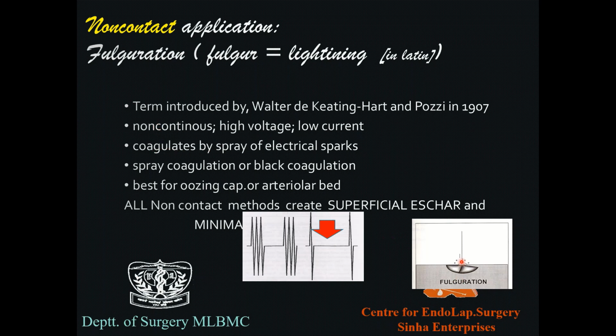See, it is spraying. The spray coagulation or black coagulation is best for oozing capillaries or arterial bed. So remember, if you have a non-contact mode, whether you're cutting or you're coagulating, it is always going to be superficial eschar and minimal damage. Why? Because your probe is not in contact with the body. There is an open circuit. It is away from the body, right?